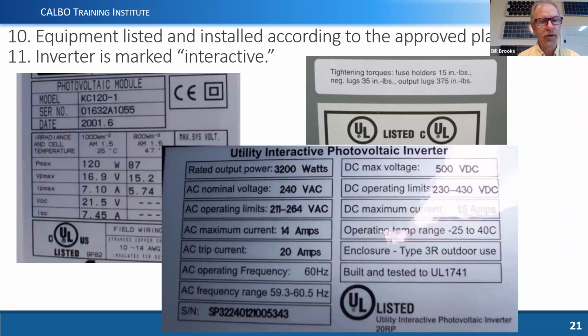Equipment listed and installed according to the approved plan. One of the things that a field inspector is tasked with doing is to make sure that any certification labels are on the equipment, and those certifications are correct and relevant to the installation. Our inverters are going to have listing labels on them. The modules are going to have listing labels on them. If we have other equipment, we'll have listing labels. If we have junction boxes and things like that, they'll also carry listing labels. And of course, our cables are marked according to the way they've been tested. We'll see that in a second.